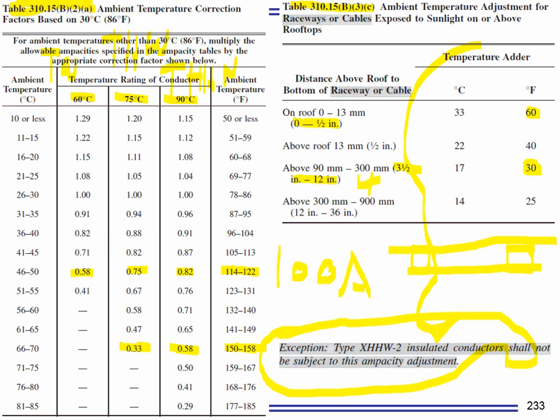Now, what if you're using THW? THW. I need somebody to correct me. We're on the roof. What if you're using this type of correction? Can I use THW on the roof? Now remember, THW, guys, is what? Rated for wet. You can't use THHN on the roof. THHN is not a conductor that has a W at the end.